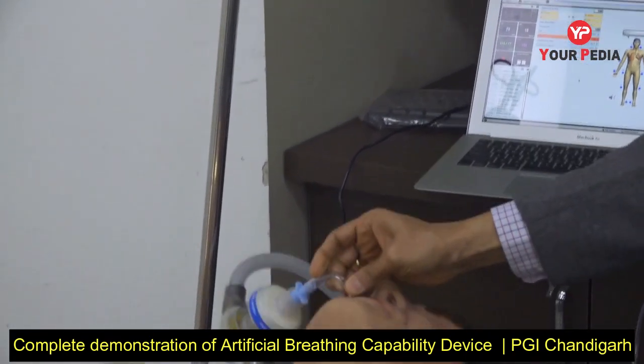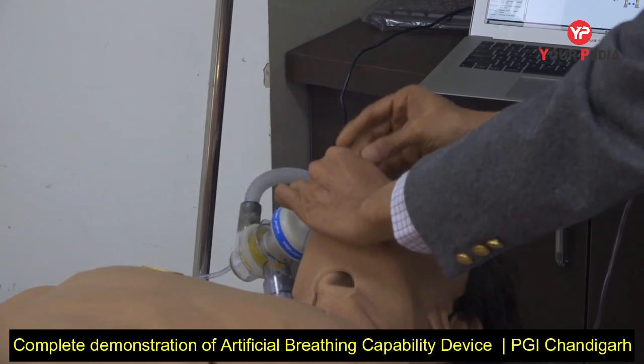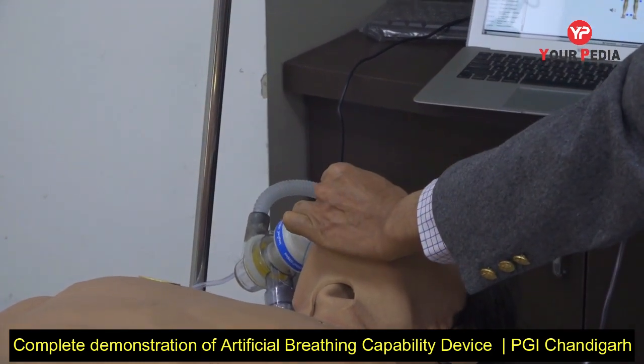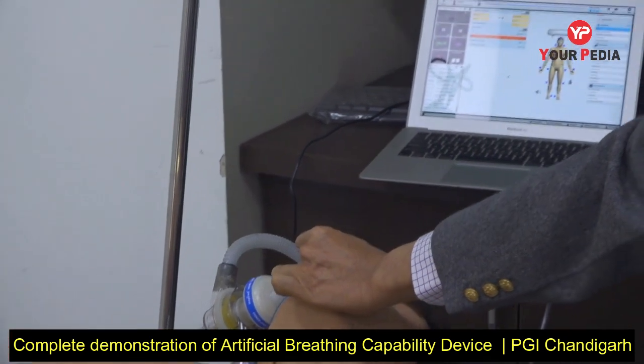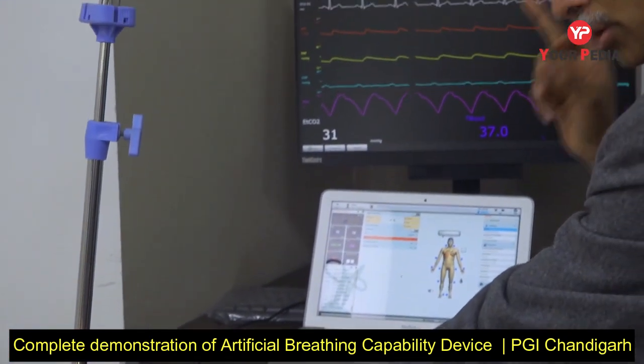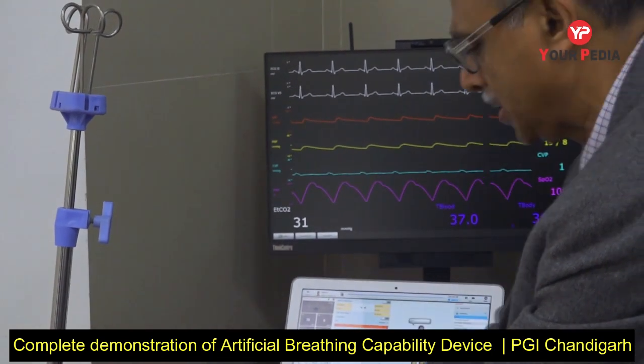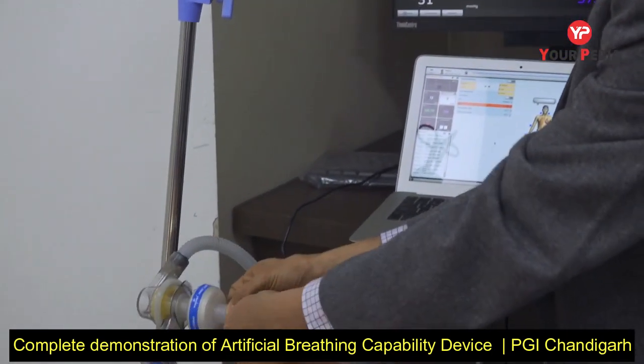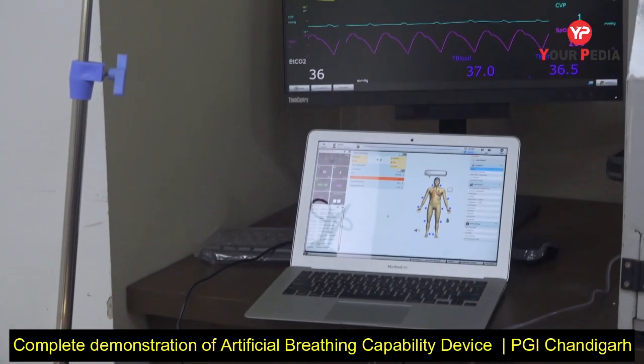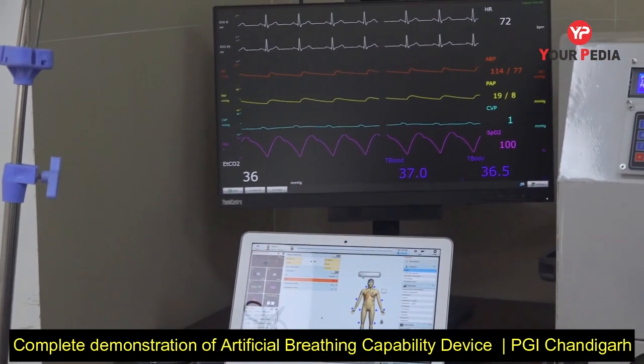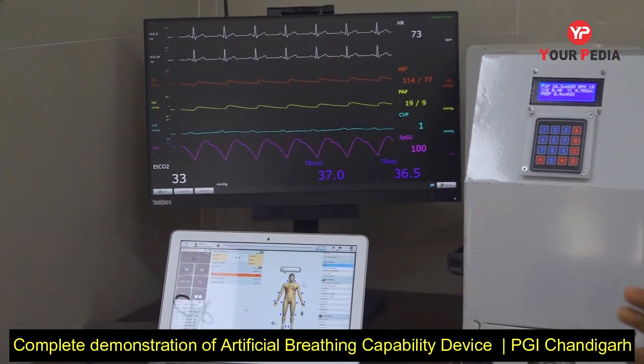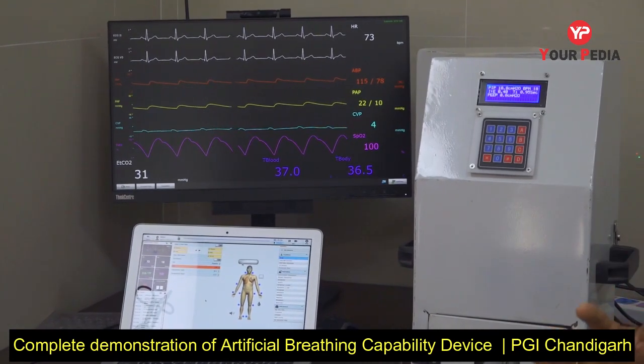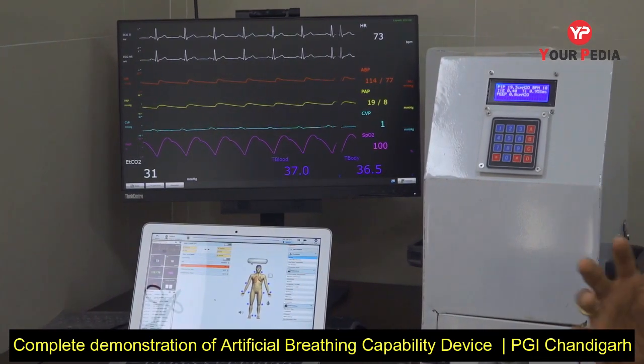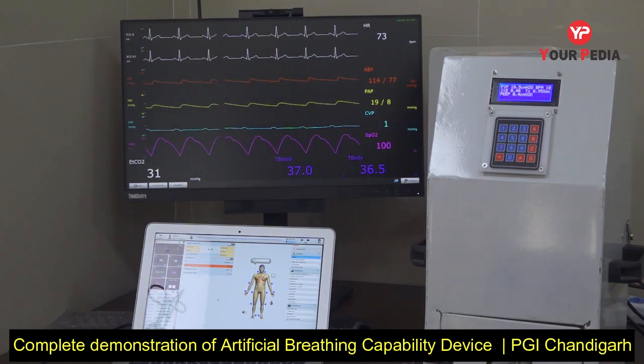We also have a tube block alarm. I'm simulating a tube block by compressing this particular tube. When that happens, again you'll observe that airflow diminishes. You'll see that there is an alarm, and the machine gives an audio and a visible alarm that there is a tube block. I'm releasing this as the patient's condition seems to have deteriorated. I release the block and immediately you find that things are back to normal again. So some of these safety features have been built in just to ensure that both the user and the patient have a relatively efficacious and safe ventilation using this artificial breathing capability device.